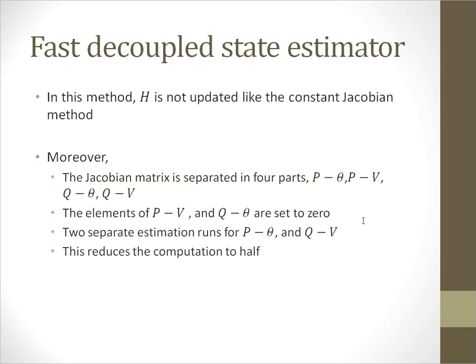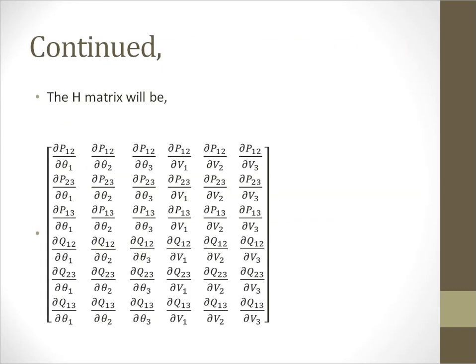We do two separate estimations for P-theta and Q-V. For example, we had the first part of the Jacobian matrix like this. It will be separated in four parts: P-theta, P-V, Q-theta, and Q-V. The elements of P-V and Q-theta will be set to zero.